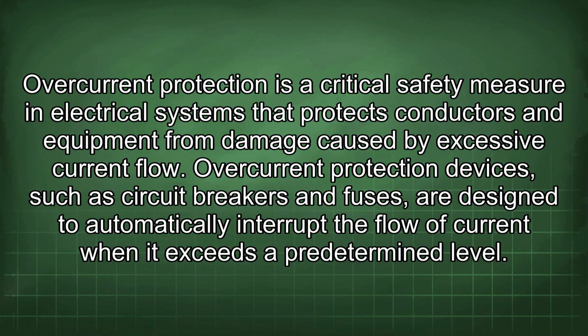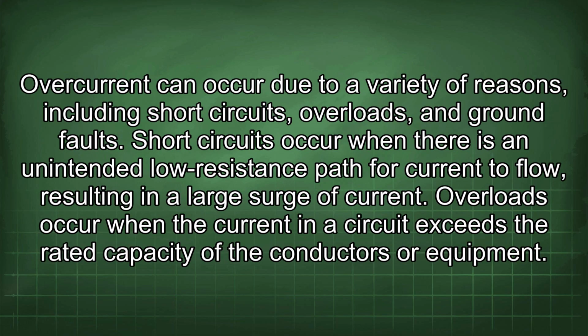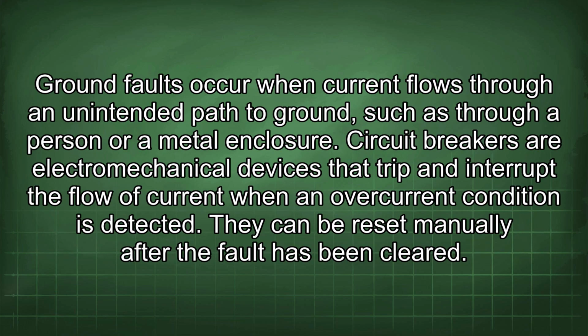Overcurrent protection devices, such as circuit breakers and fuses, are designed to automatically interrupt the flow of current when it exceeds a predetermined level. Overcurrent can occur due to a variety of reasons, including short circuits, overloads, and ground faults. Short circuits occur when there is an unintended low resistance path for current to flow, resulting in a large surge of current. Overloads occur when the current in a circuit exceeds the rated capacity of the conductors or equipment.